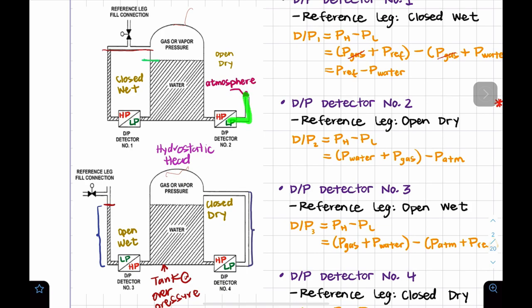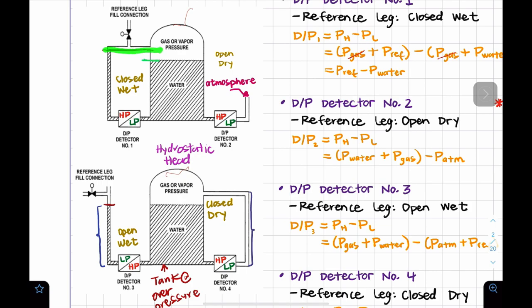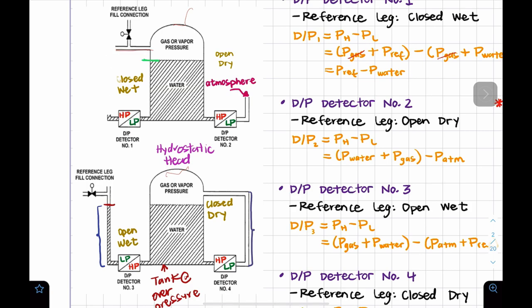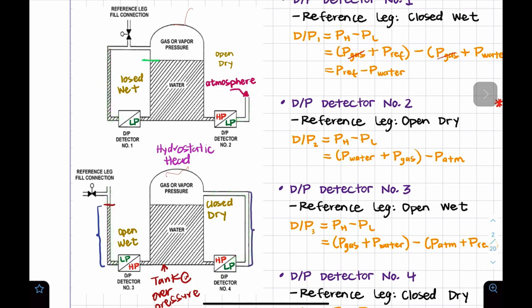The reference leg is usually the low pressure side. We'll see why detector number one has the high pressure level detector on the reference side. We'll have a reference leg, and it can be either wet or dry. A dry reference leg means it's empty; a wet reference leg means it's filled with liquid. A wet leg avoids measurement error caused by vapor condensate in the reference leg.